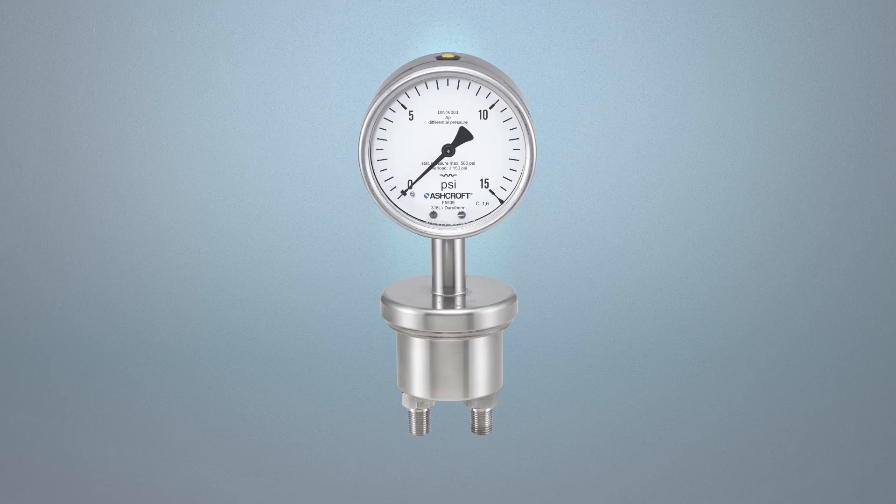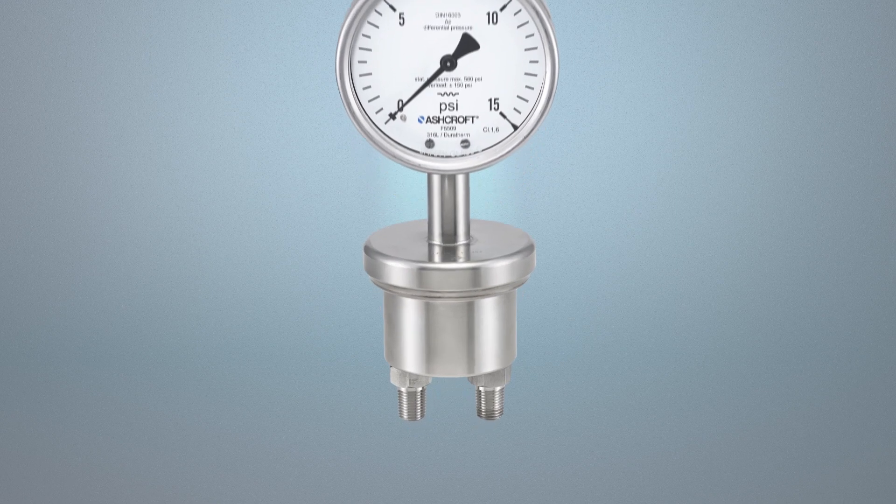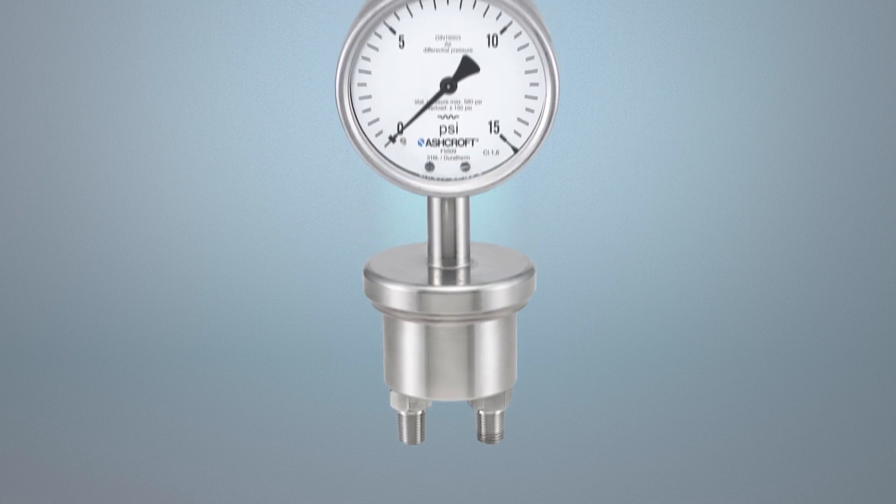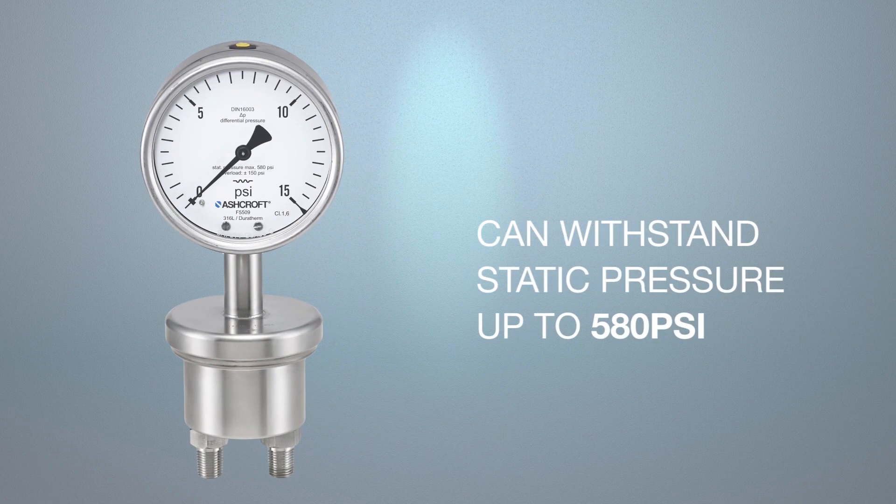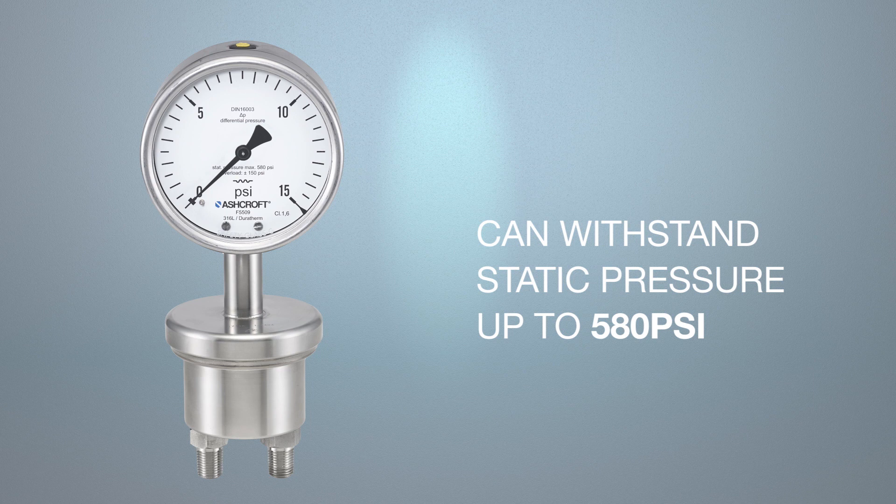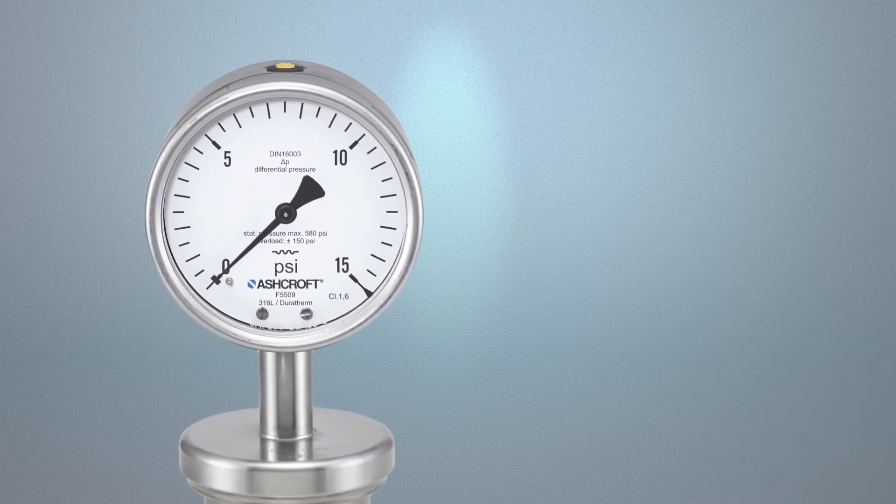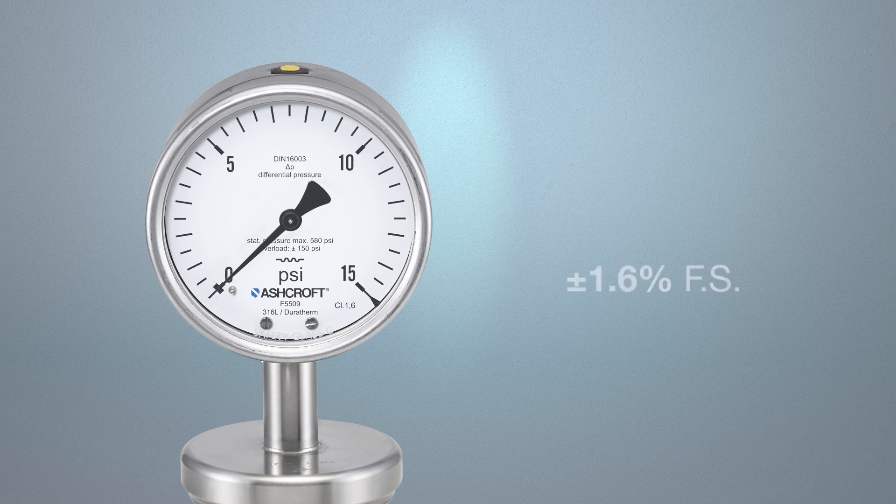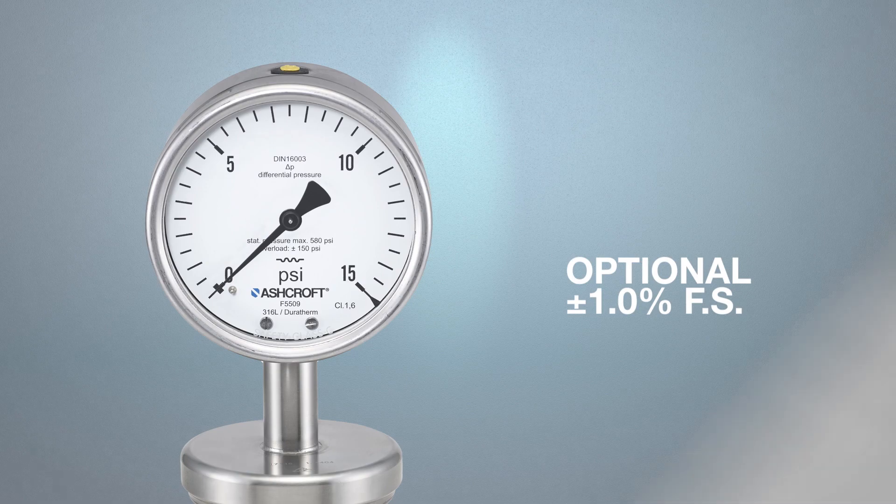The all welded F5509 open front and F6509 solid front differential pressure gauges can withstand static pressures up to 580 PSI, eliminating the risk of catastrophic failure due to excessive pressure. And it can deliver differential pressure readings and accuracies of plus or minus 1.6 or 1% of full span.